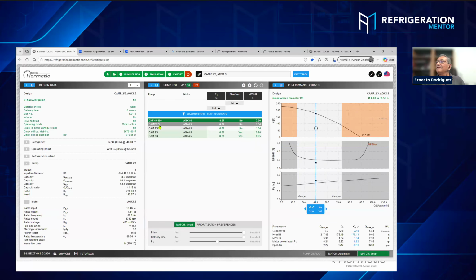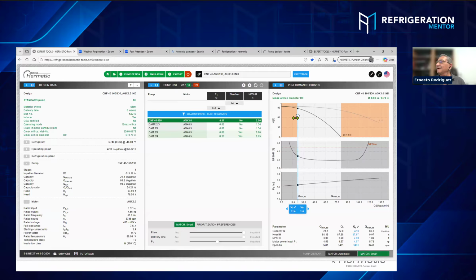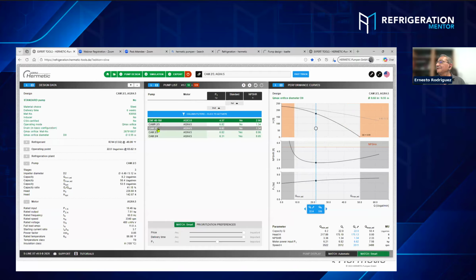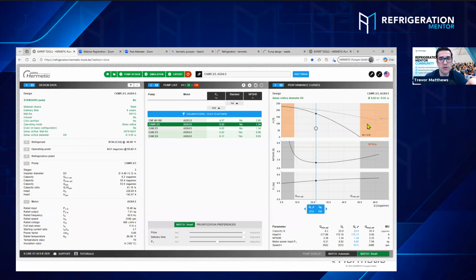For example, in these options, this pump has one impeller that is very close to the curve. It's very tight, you can see right here, and the pressure is too high. Let's go to the next pump, number three. It's a much better pump application. The orange area, you don't want to be touching that. Orange means you exceed the capacity of the motor.